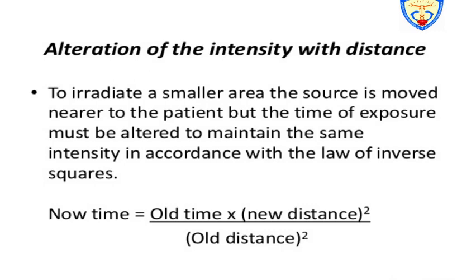There is also a formula for alteration of intensity with distance. To irradiate a smaller area, the source is moved nearer to the patient, but the exposure time must be altered to maintain the same intensity according to the inverse square law. The new time is calculated as: old time × (new distance)² ÷ (old distance)².